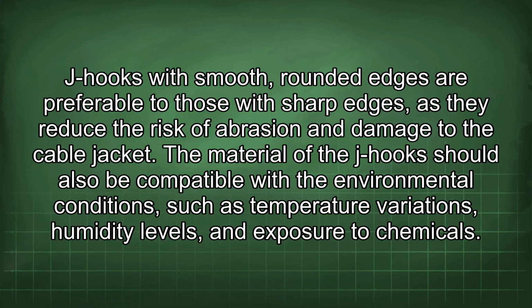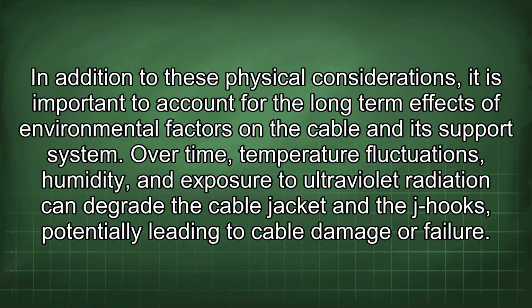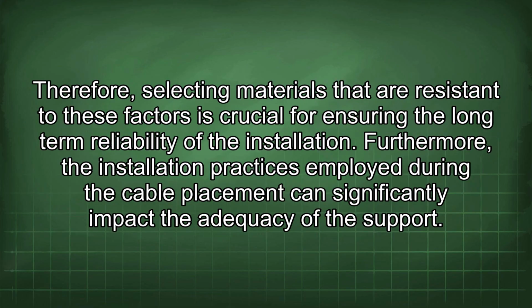The material of the J-hook should also be compatible with the environmental conditions, such as temperature variations, humidity levels, and exposure to chemicals. In addition to these physical considerations, it is important to account for the long-term effects of environmental factors on the cable and its support system. Over time, temperature fluctuations, humidity, and exposure to ultraviolet radiation can degrade the cable jacket and the J-hooks, potentially leading to cable damage or failure. Therefore, selecting materials that are resistant to these factors is crucial for ensuring the long-term reliability of the installation.